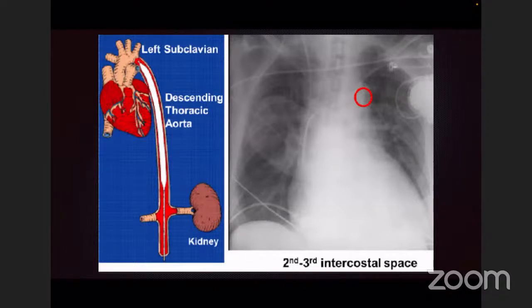So how do we confirm this positioning? One is via transesophageal or transthoracic echocardiography. The other thing is in the form of an X-ray. On X-ray, we can usually see a radiopaque balloon tip. That should lie just above the carina, which will coincide with the second or the third intercostal space. Or usually, when IABP is inserted in the cath lab, there you do direct fluoroscopy, you can very easily see where the balloon position is, and you can also very beautifully see how the balloon inflates and deflates in real time in the cath lab.